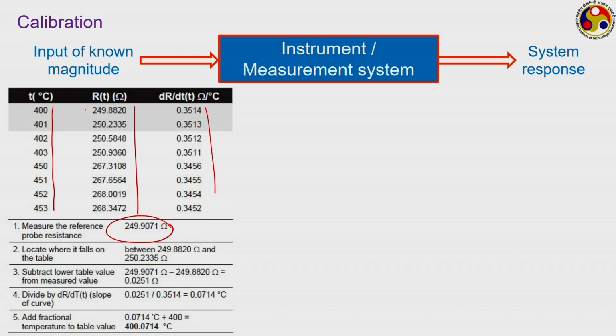In this particular case, it is falling in between these two values. Then we perform some kind of interpolation, that is, subtract the lower value from the measurand and then divide that by the corresponding slope, which is 0.3514 in this example, and with the final addition that is going to give you the final temperature of the unknown quantity. So, during any calibration process we have to find a calibration chart to identify the correspondence with this.